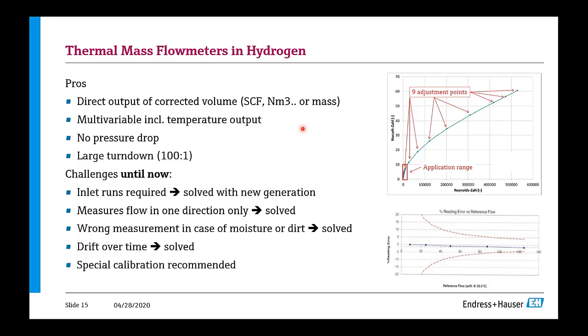When it comes to thermal mass, hydrogen is, I must say, quite a challenging gas because of the measuring technology itself. The thermal mass provides you directly the mass or the corrected volume of your hydrogen. It's multivariable, you don't have pressure drop, you've got a large turndown, and you can also measure at these ranges. However, you see here, this is where we calibrate our meters on air, and this is where you use the meter in hydrogen. So the characteristics are quite a little different. That's why in the US, very often these meters are actually recalibrated on hydrogen. That's done by the OEMs we have there.